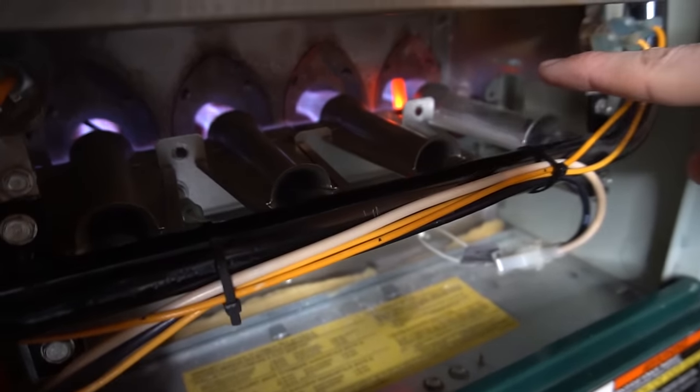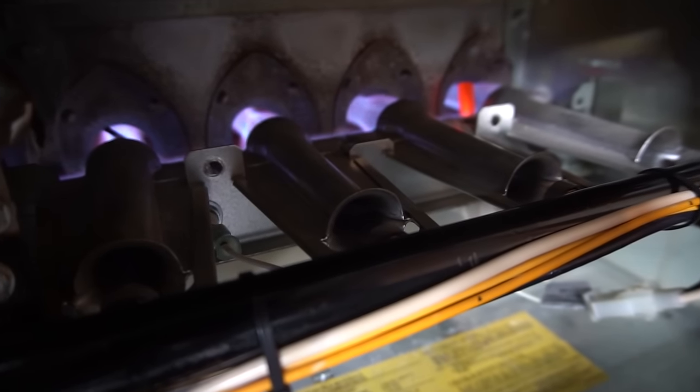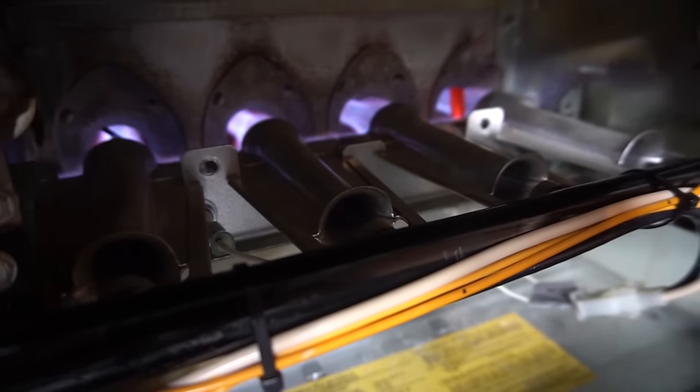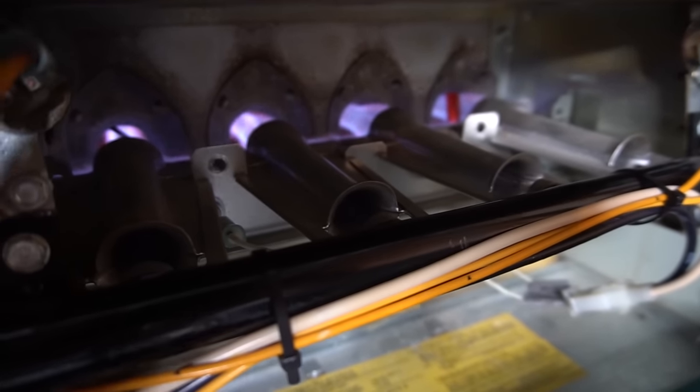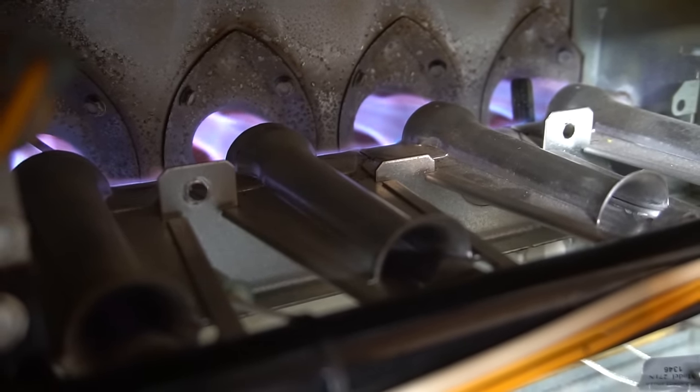See how the flames are just getting sucked in real nice? I have a two-stage furnace. This is the low stage, which is why the flames look a little smaller than usual. This is how a normally operating furnace would look like.